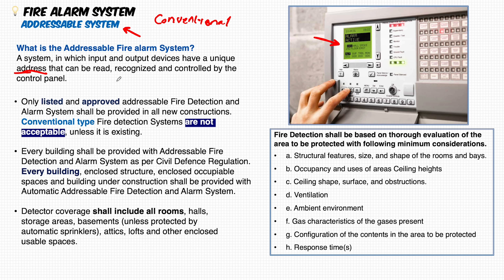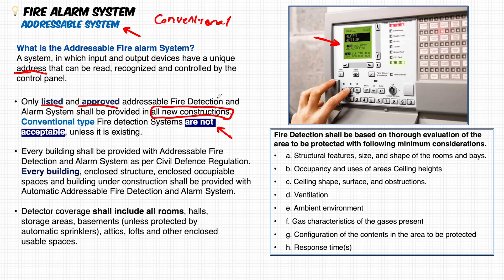What does the UAE regulation say about addressable fire alarm systems? Only listed and approved addressable fire detection and alarm systems shall be provided in all new constructions. Any new building after the UAE Fire Life Safety Code 2018 shall use addressable fire alarm systems — the conventional type is not acceptable for new constructions.